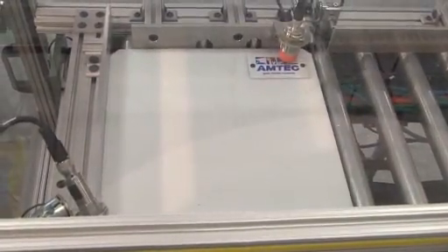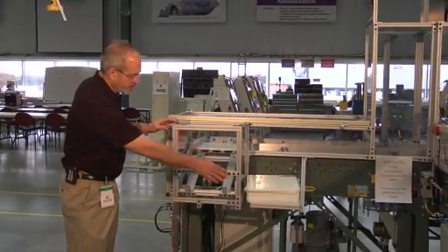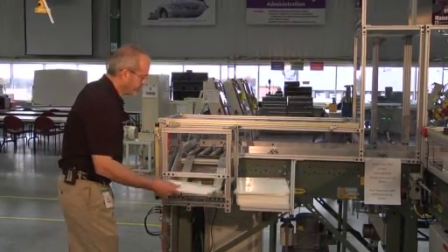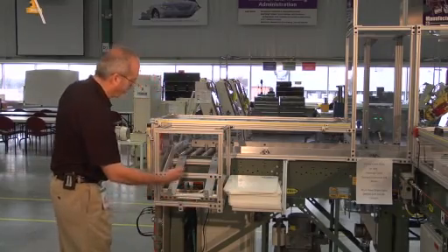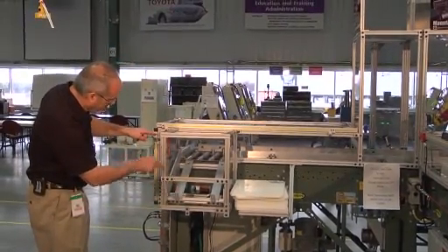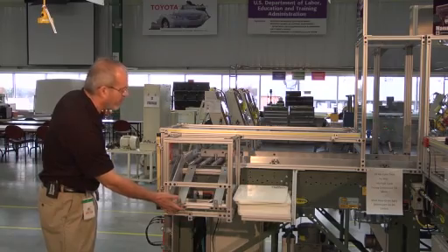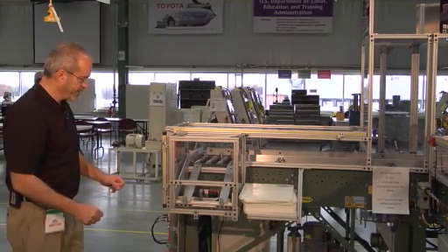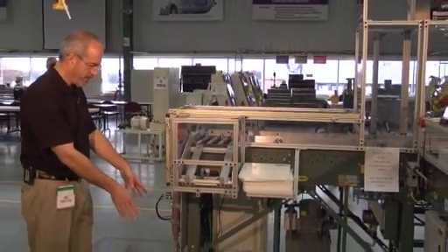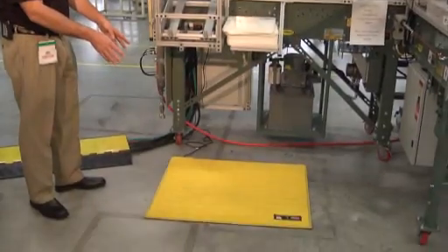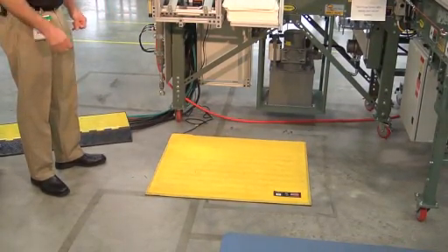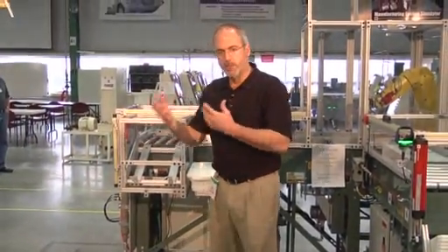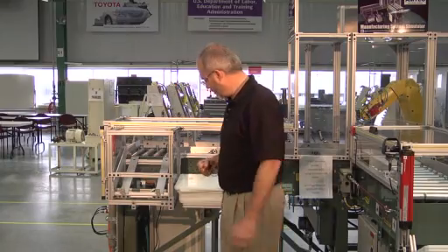We're now at the unload side of the conveyor here. We have our storage unit for the pallets as they come off. This is fully enclosed guarding so that you can't reach up and in. We've got another photo eye here that detects that there is a part in the storage area. And the last physical safety component we have is on the floor here, which is an industry safety mat, typically used around a robot cell so that when a person stands on the safety mat, the robot doesn't move, so there can't be any interaction between a human and a robot.